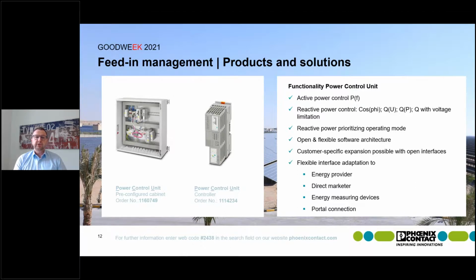For reactive power, you can choose between different characteristics, because these are requested by the European grid codes as well as the German guidelines. That means controlling reactive power according to cosinus phi, based on voltage, based on power, or reactive power with voltage limitation. Those are all the different characteristics required by the European grid codes.